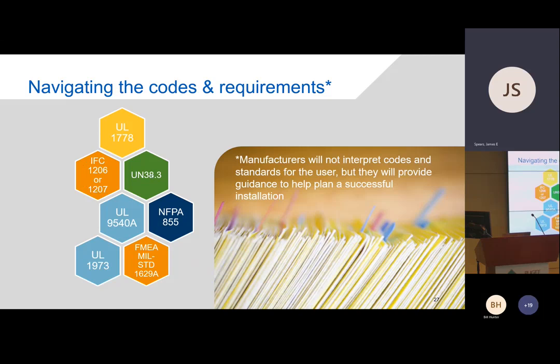We mentioned UN 38.3 and UL 9540A. The other standard cited most often is NFPA 855. The requirements for lithium battery installations in NFPA 855 and Fire Code 1207 are very similar, but we shouldn't assume they're identical—we need to be familiar with both in case there's a minor difference.